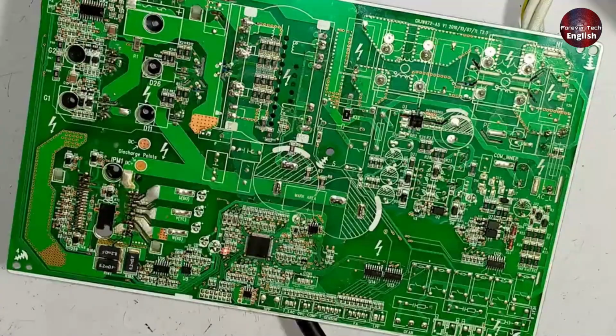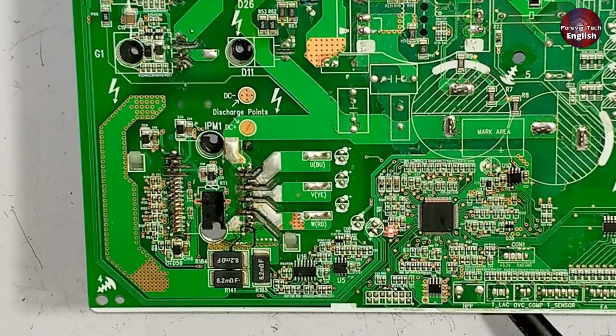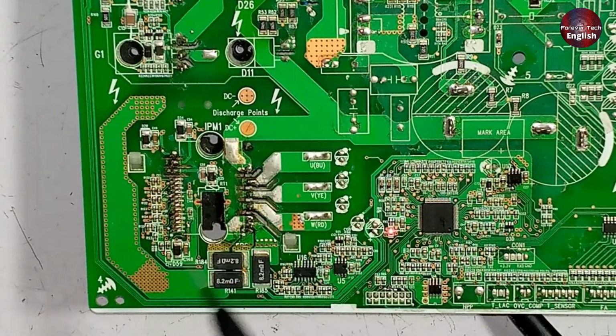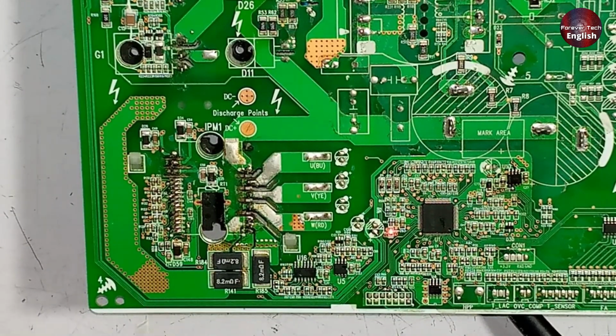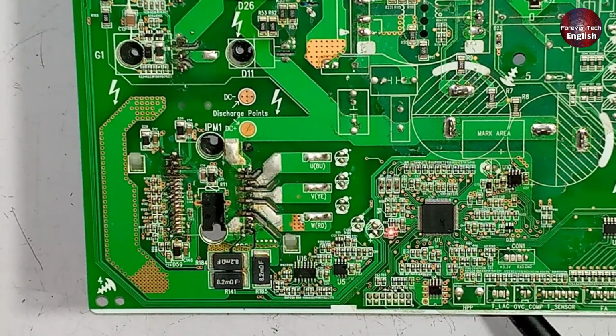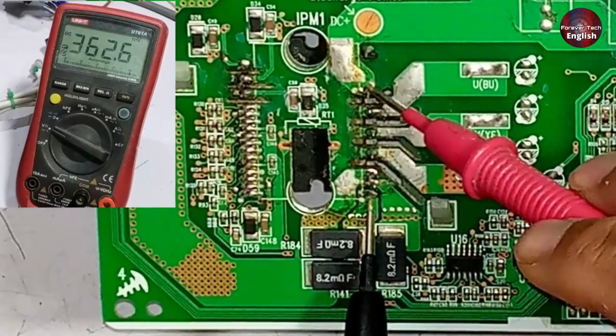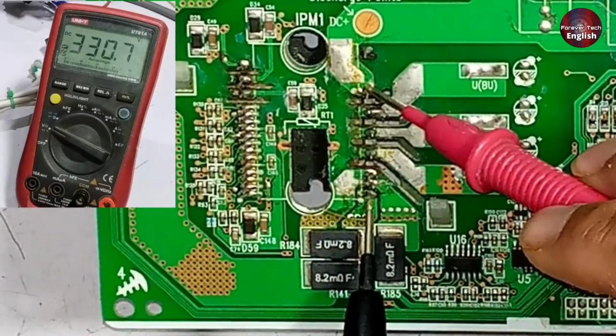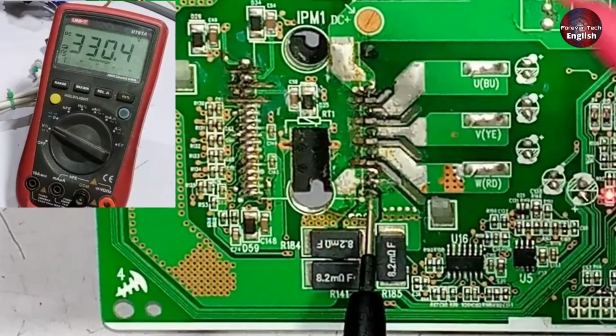The next point to check is the IPM. You need to verify the voltages present on the IPM. When examining the IPM, there are 2 sides, the low side and the high side. On the low side, you should get 15 volts, and on the high side, you should get 327 volts. Checking between the negative and positive terminals, the reading shows 330 volts, which is correct.